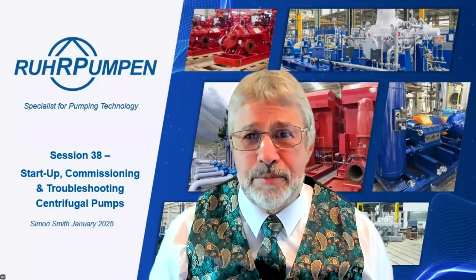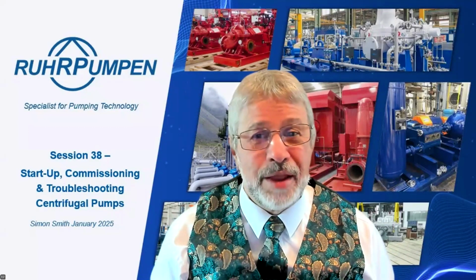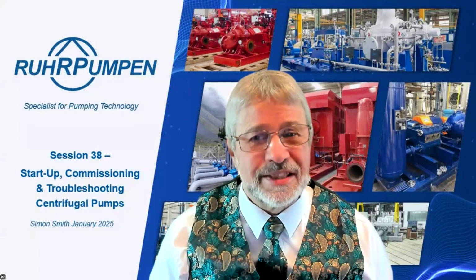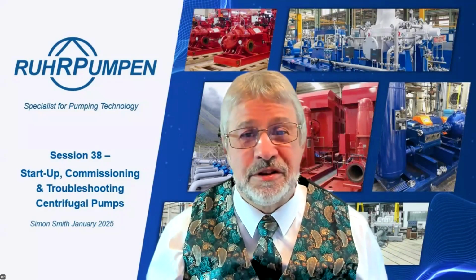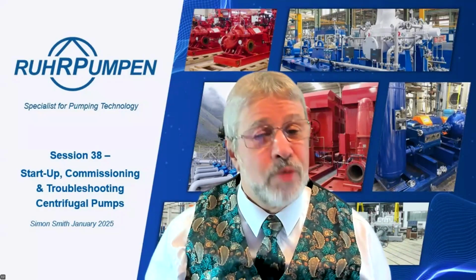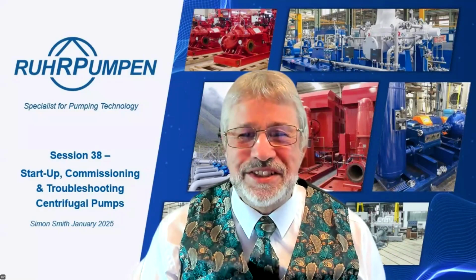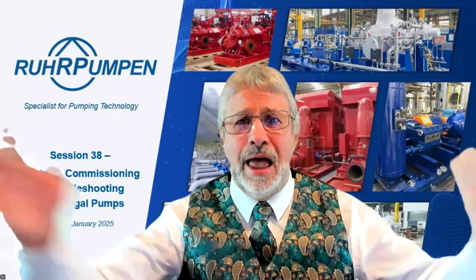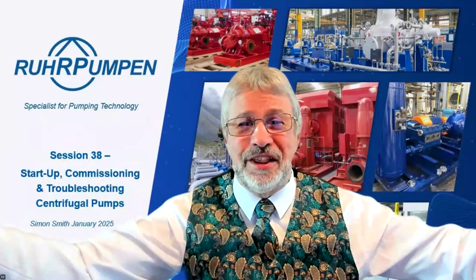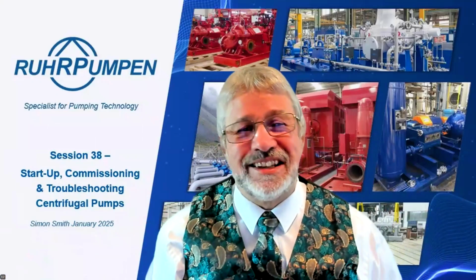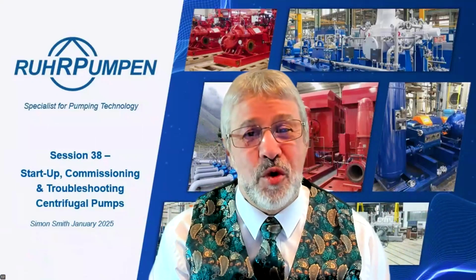BB3, BB5 pumps, these are very reliable pumps. They're being used in the oil pipeline business all the time, and they've been well established. So there's no reason not to be using those. Probably better than having a high speed pump for those operations. But it's very hard to answer that question because it's really how long is a piece of string? I would need to have a look at the precise operating conditions you want, and then we'd be able to make a recommendation, as would any other pump manufacturer.